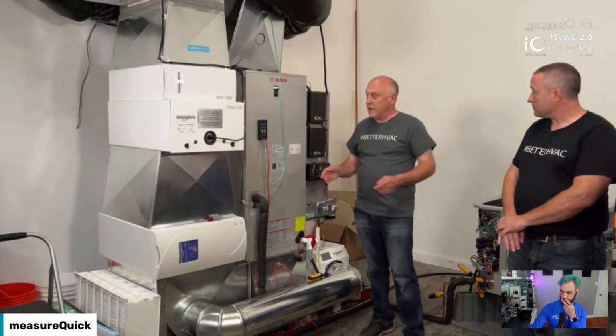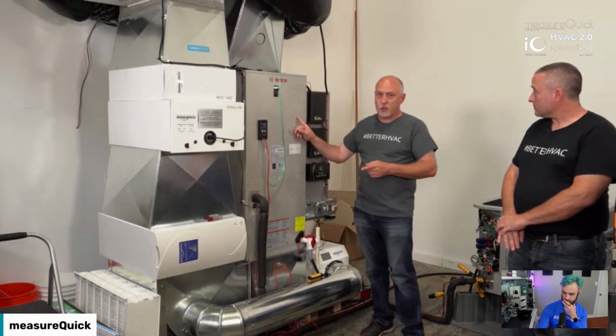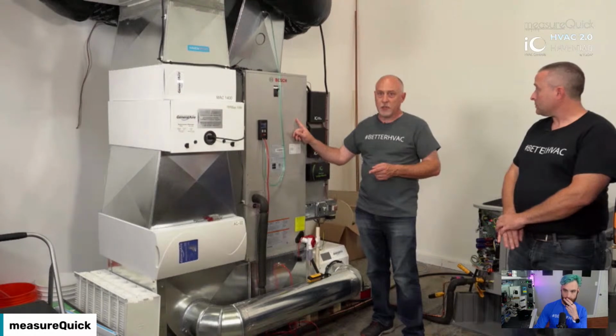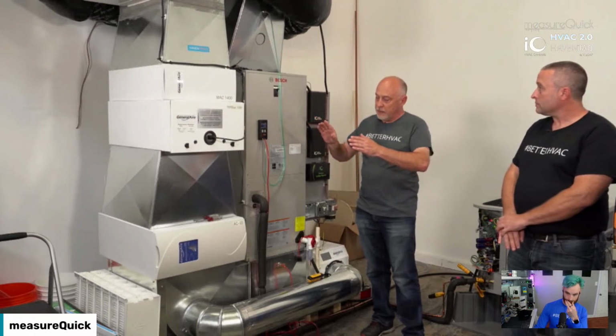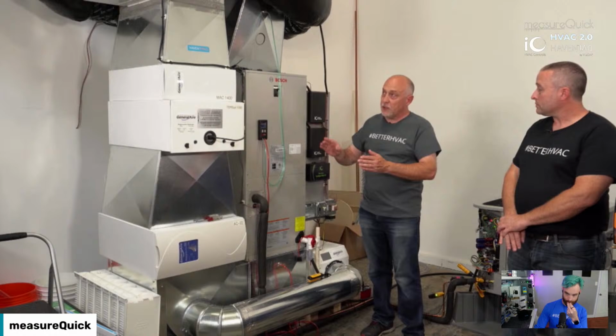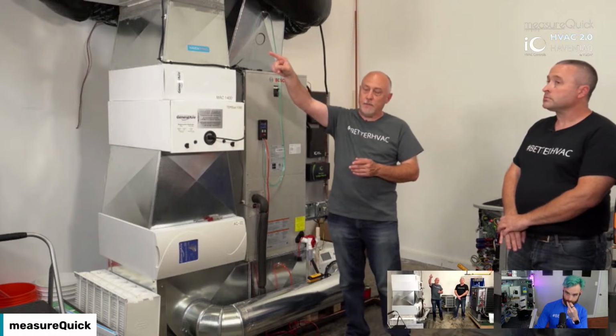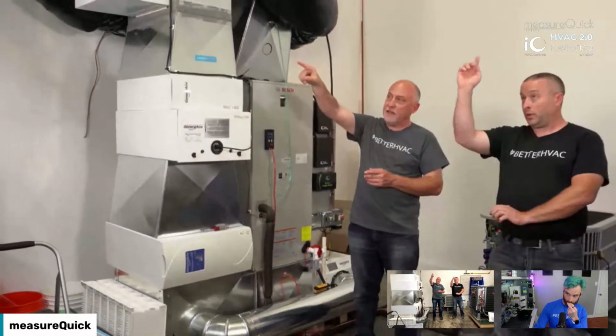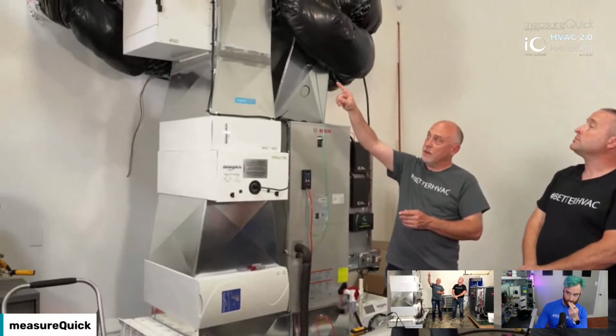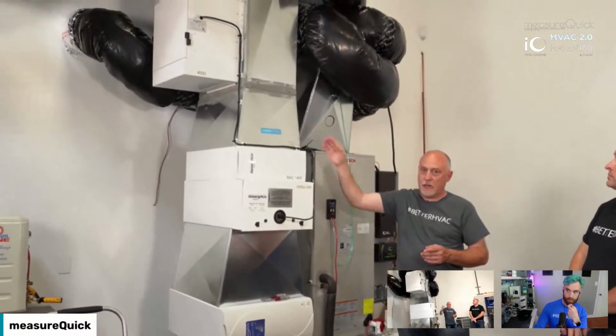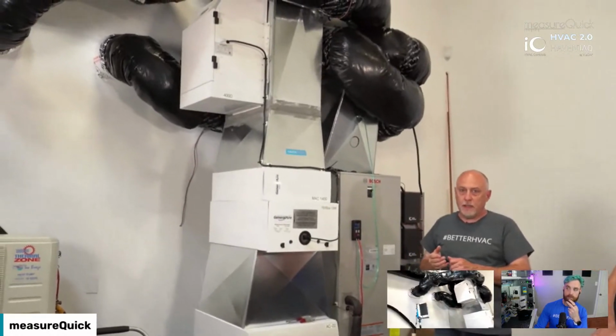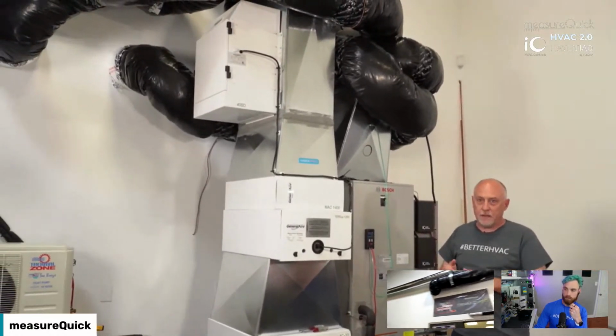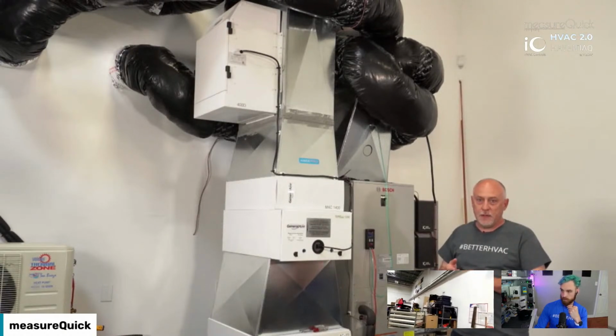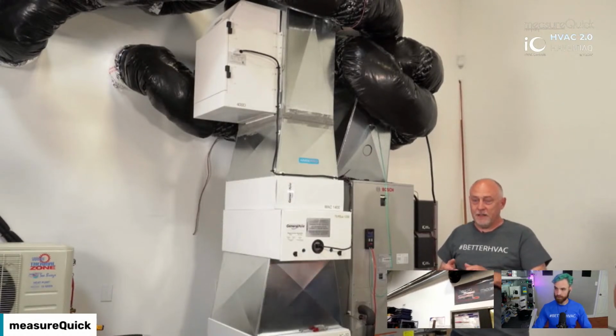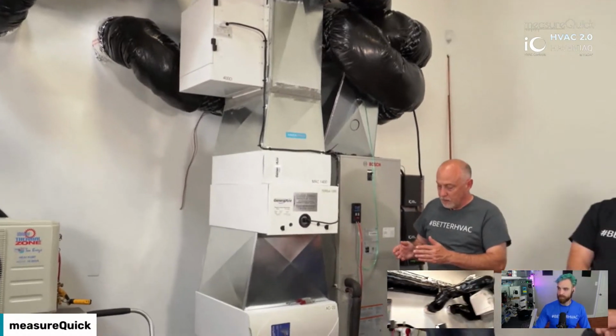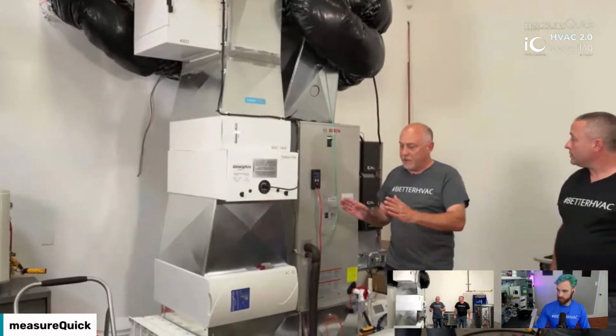And then Nate just got done tying in electric reheat in the air handler, so we can do electric reheat. It's really tied around quite a few different things. We also brought in outdoor air, so we've got a duct that's about 80 foot long that goes back to the end here and ties the outdoor air into the return air drop. So basically we're able to control the ventilation, the filtration, the dehumidification, the humidification, all in this system. There's a little bit of everything going on here.